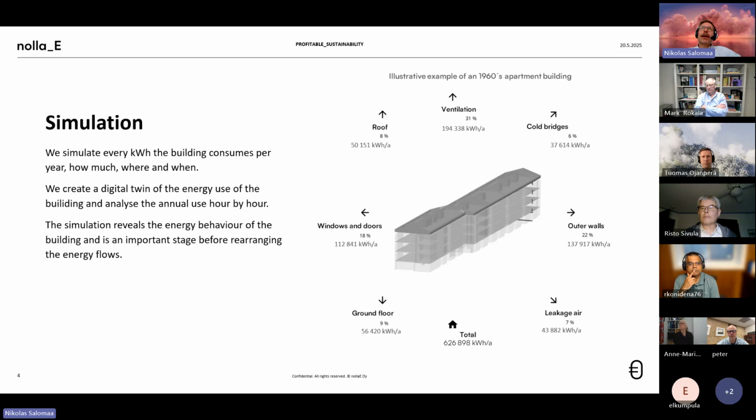For big ventilation units, like if you have a central ventilation unit for a building, the software wants to know what is the manufacturer and model of the supply air fan, what is the model of the exhaust fan, what heat recovery is there, what is the manufacturer of that one, and which model, and so on. All the different details of the ventilation unit.